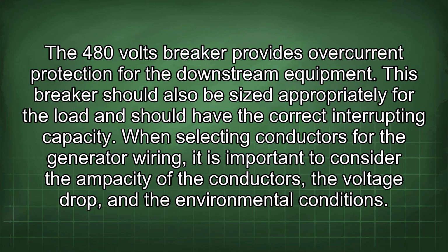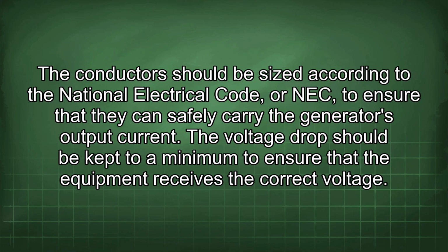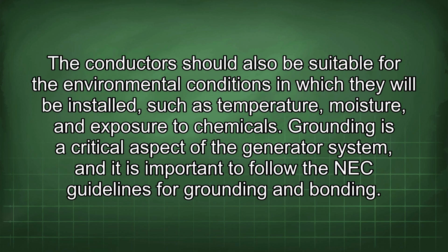When selecting conductors for the generator wiring, it is important to consider the ampacity of the conductors, the voltage drop, and the environmental conditions. The conductors should be sized according to the National Electrical Code, or NEC, to ensure that they can safely carry the generator's output current. The voltage drop should be kept to a minimum to ensure that the equipment receives the correct voltage.